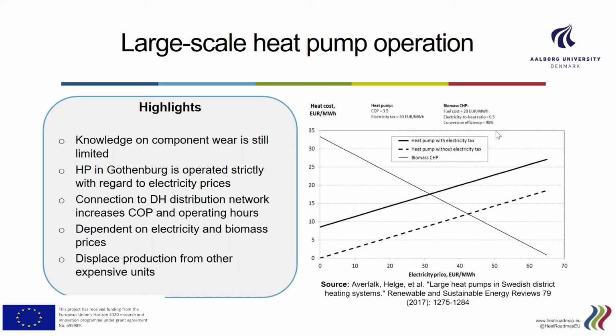A concern is the mechanical wear that appears during startups. Experiences from Sweden show that daily startups are close to the limit of normal operation but still acceptable for large electrical engines, which are generally the most vulnerable part of the heat pump. For example, the very old heat pump in Gothenburg has been operated strictly with regard to electricity prices since the beginning of the 1990s, with few or no mechanical issues because of this way of operating it.